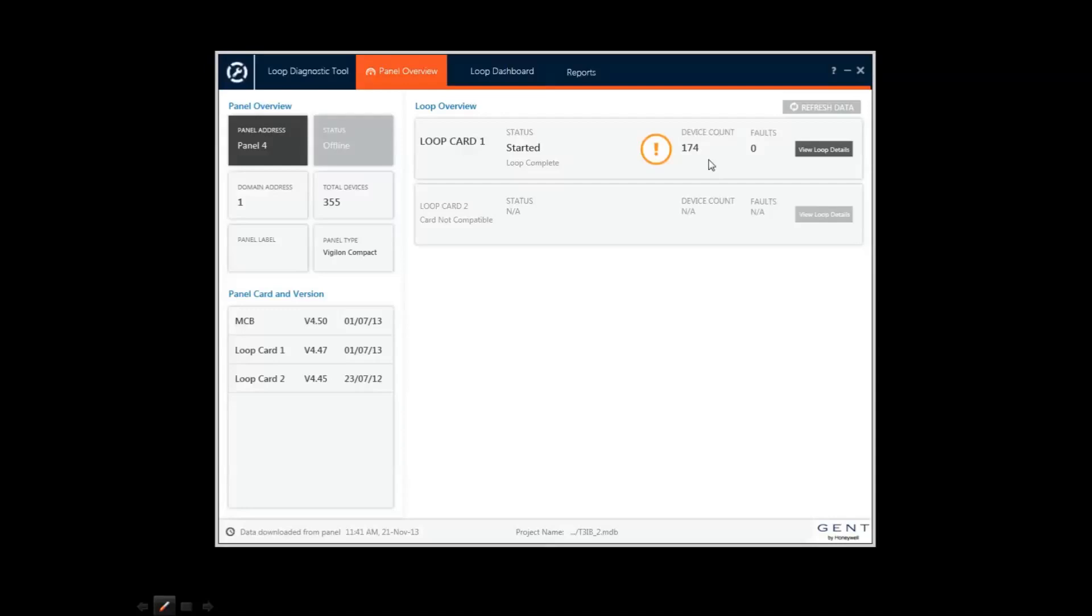The tool identifies any issues with simple status indicators. Here the exclamation mark shows there is a potential issue on loop 1. I can click on the button here and see a detailed diagnostic summary for that loop.